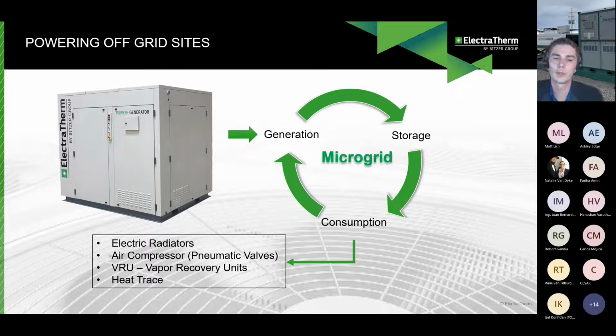Currently, utilizing this equipment for off-grid sites, since we're utilizing an induction generator, you would couple this equipment with batteries and inverter systems. We're also working on standardized packages expected to release in 2023 for island mode sites, so sites that don't have any site power whatsoever.